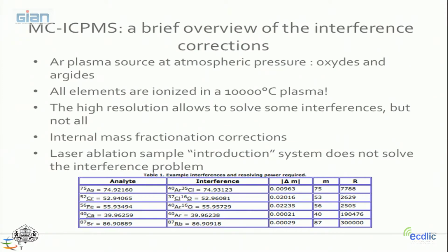You can still, like for TIMS, resolve the mass fractionation correction using the stable isotopes, but with the multi-collector ICP-MS, you can also add some elements which have roughly the same mass, sitting, for example, in the middle of lead, and use the fractionation on this element to correct all the others. Typically, we use thallium. Thallium has masses 203 and 205. Sitting right in the middle, we measure the fractionation of thallium, and we apply this fractionation to lead. This is something you cannot do with the TIMS.